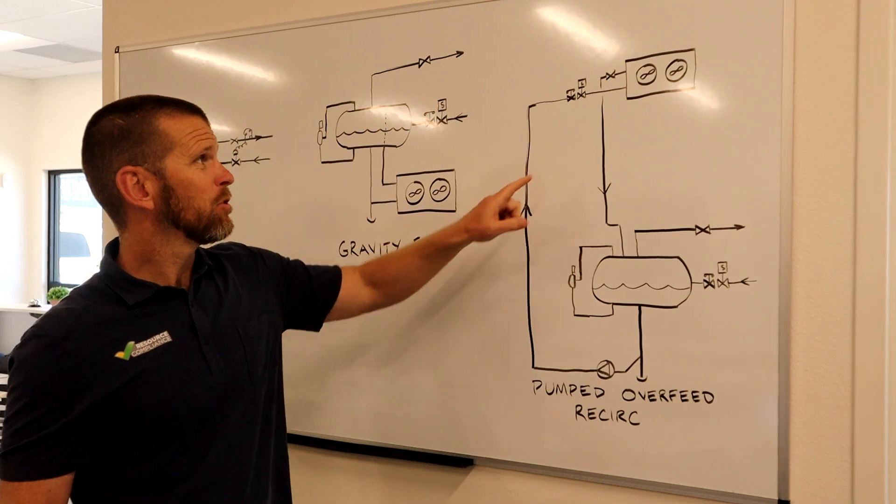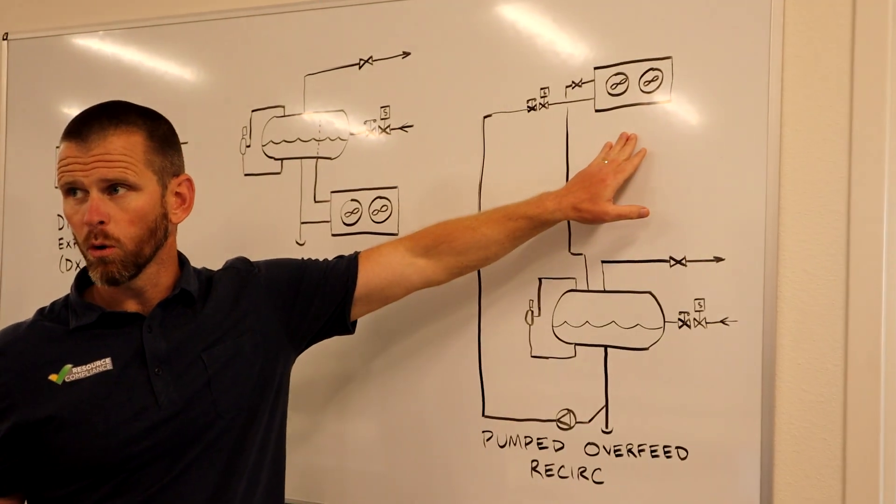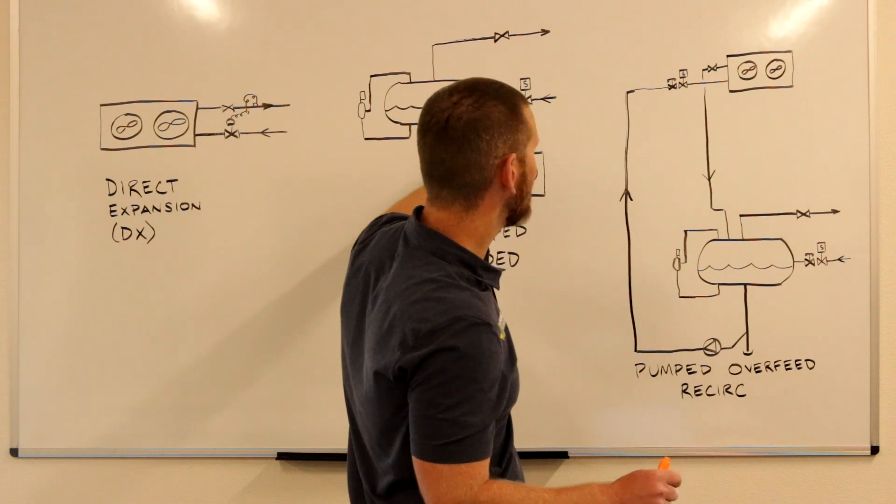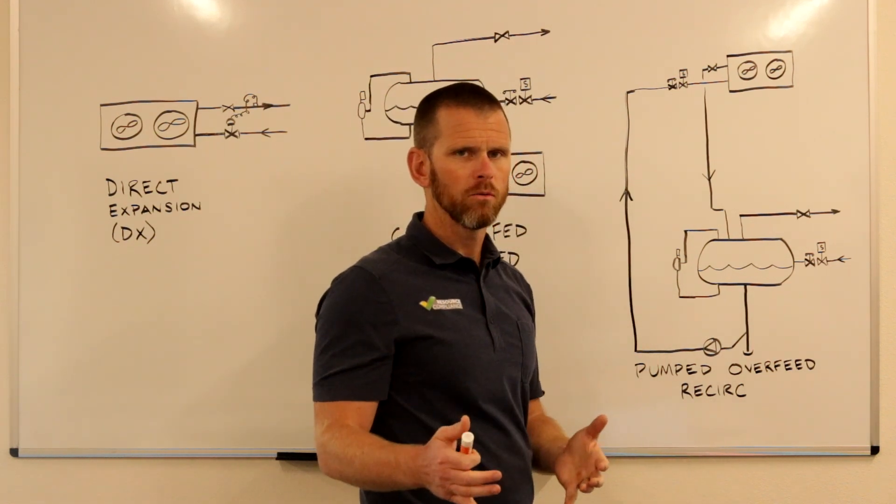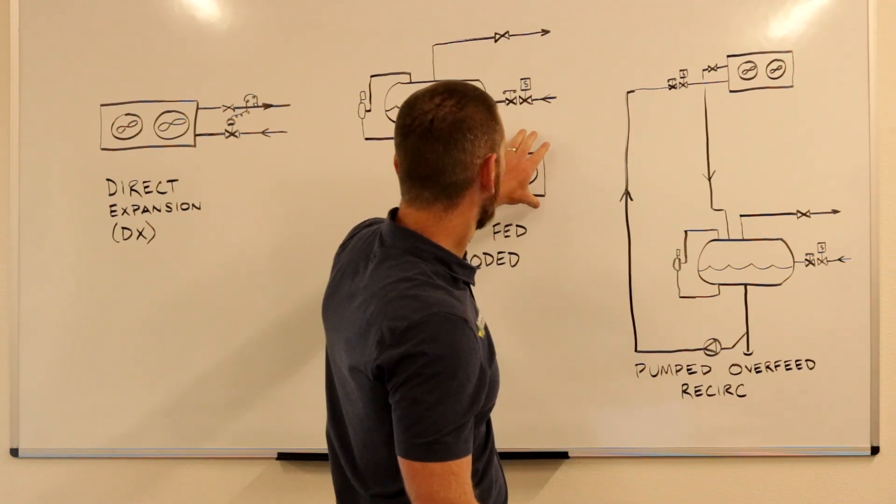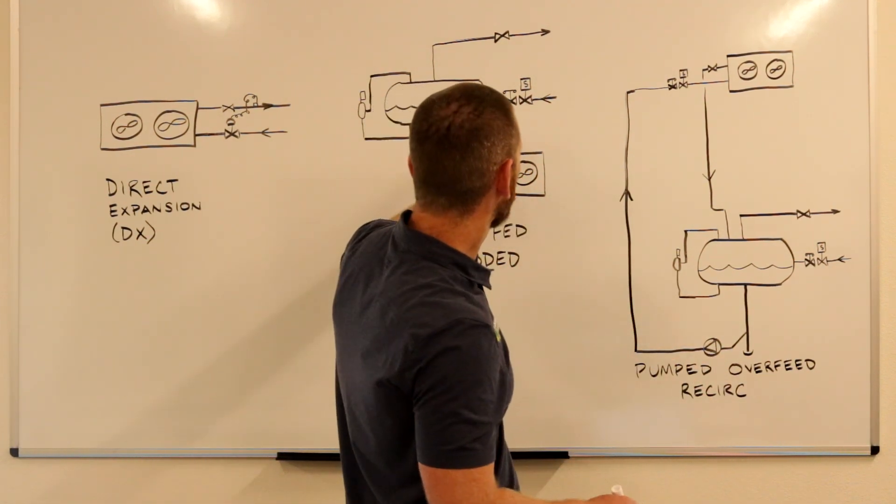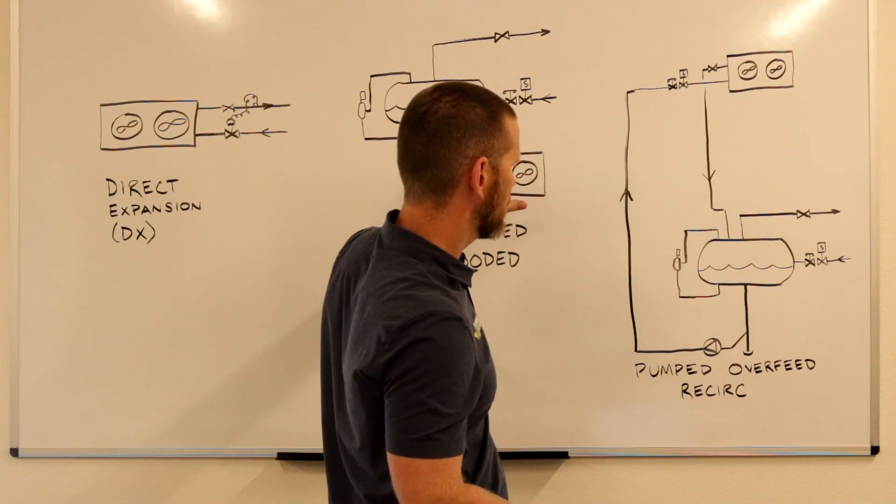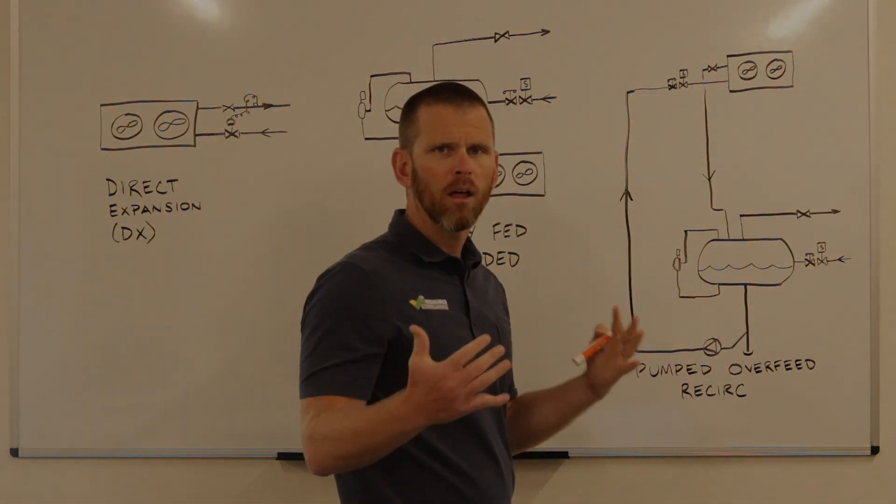The downside of this system is you don't get quite as precise of temperature control compared to a flooded system when we're talking about individual rooms or zones. Having a surge drum per zone or per room allows you to precisely set a temperature in a flooded system, whereas the recirc systems, you don't have quite the same level of control.